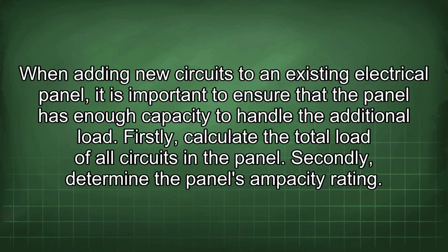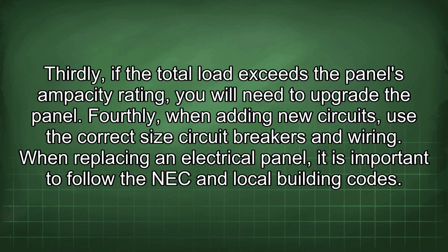When adding new circuits to an existing electrical panel, it is important to ensure that the panel has enough capacity to handle the additional load. Firstly, calculate the total load of all circuits in the panel. Secondly, determine the panel's ampacity rating. Thirdly, if the total load exceeds the panel's ampacity rating, you will need to upgrade the panel. Fourthly, when adding new circuits, use the correct size circuit breakers and wiring.